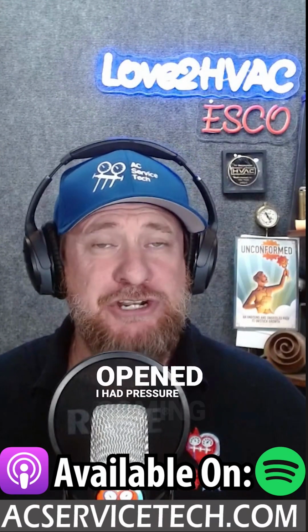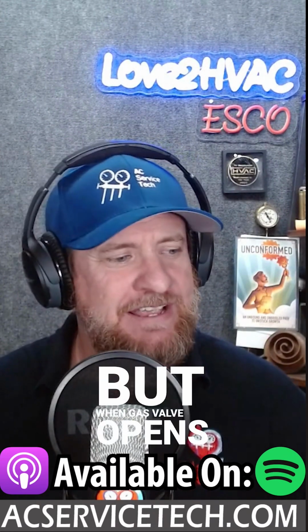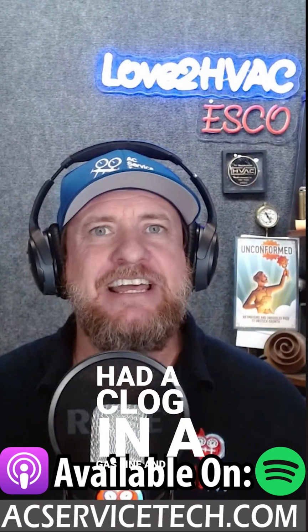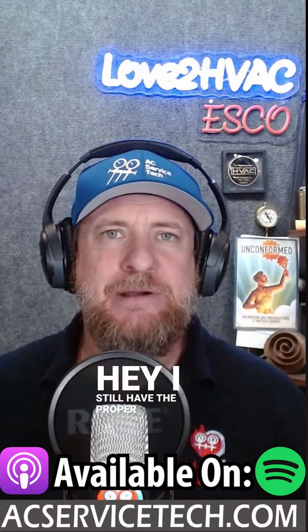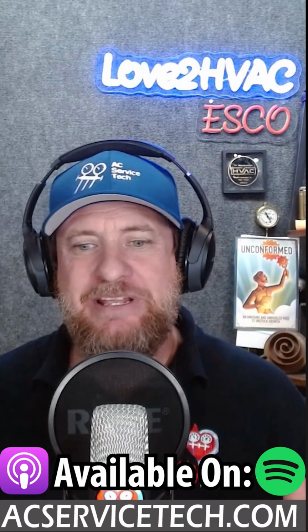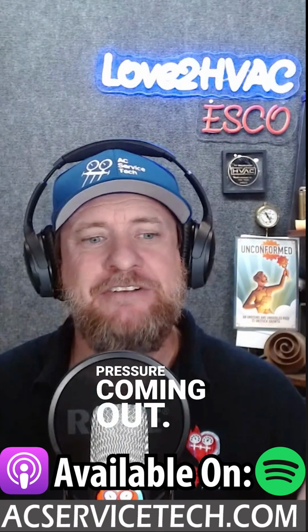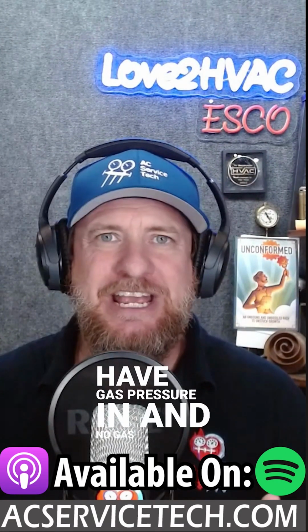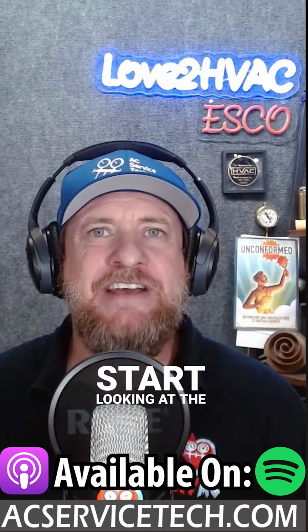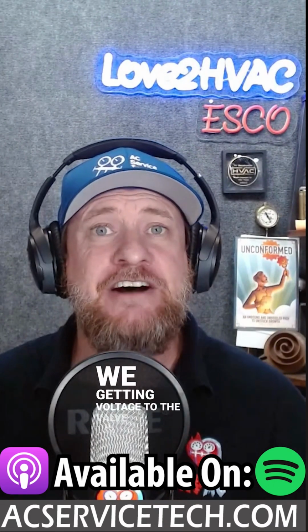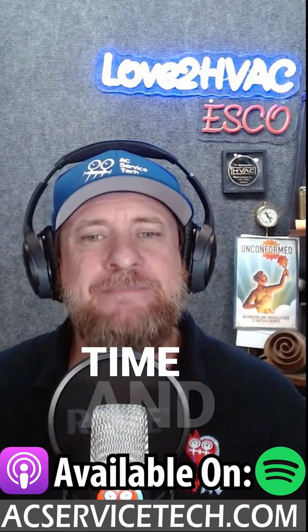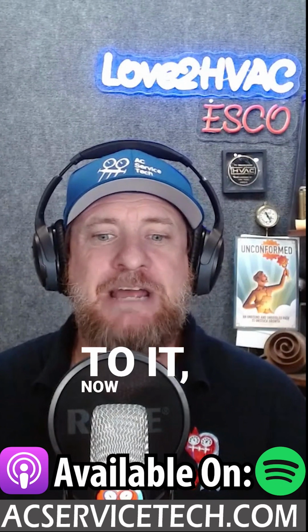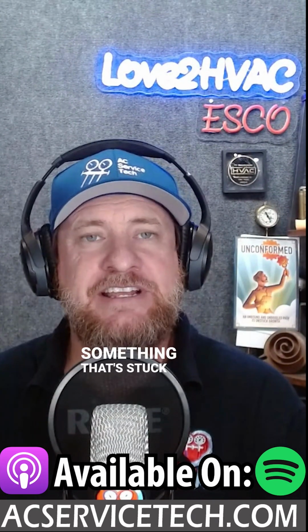And I've had it before where, when the gas valve opened, I had a clog in the gas line and I would lose gas coming into it. So being able to check on both sides, hey, I still have the proper gas pressure coming in, and then we can say, hey, I don't have any gas pressure coming out. So if we have gas pressure in and no gas pressure coming out, now we can start looking at the valve. Are we getting voltage to the valve during that specific sequence of time? And if we are getting voltage to it, now we can start looking at the valve. Maybe something's clogging it up. Maybe we have something that's stuck inside of there.